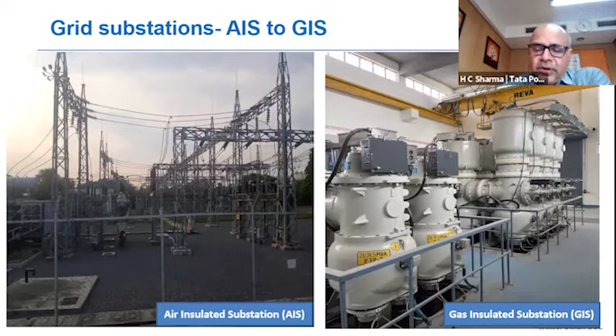Going further, then we have gone for the digital substation. I will just touch upon that. What is the digital substation? Basically, in digital substations as of today, we have done away with the requirement of copper cables and all those things. Now the system has a very smart type of cable, only one cable or two cables running from the field equipment at your bay to your substation. And then you have a process bus and a station bus. You have a process bus where all your field equipment is connected and your relays are getting connected. And then you have a substation bus where all your bays are getting connected.